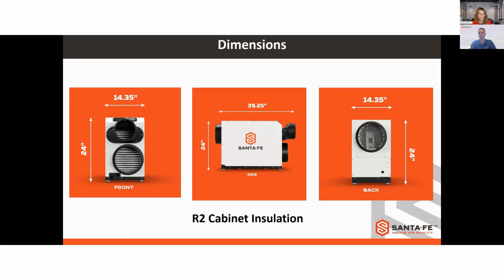This dimension, that 14.35, allows us to fit in between floor joists. So it makes it really easy to be able to set these into places that might be a little bit tighter for installation. And then all of our cabinets now have R2 insulation in them. This does help tremendously with sound from the unit, as well as minimizing the potential for condensation when we're placed in vented attics or vented crawl spaces.